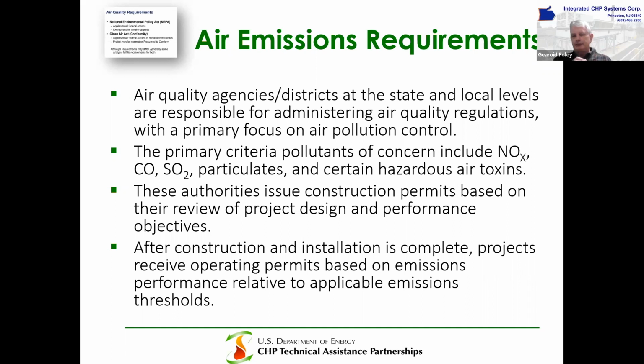If you're doing biofuels, that would be a different story. If you're doing wood, there's quite a bit of sulfur in wood, so it may be a concern depending on your fuel type. Generally for natural gas, I'm really concerned with NOx primarily. And it depends on your region's environmental compliance status with federal air regulations—whether it's in compliance or non-compliance—as to how much treatment you need to add to your box.